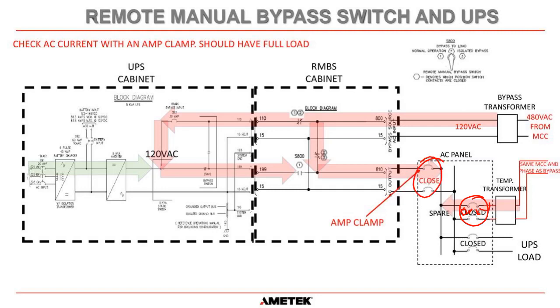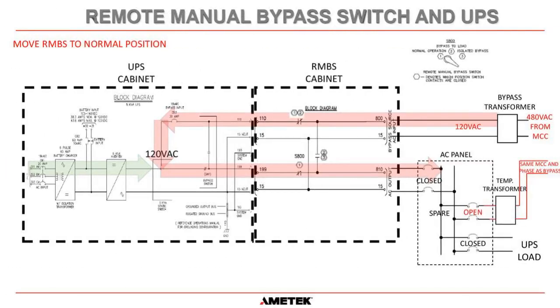We are now back in normal operation, and all we need to do now is get the UPS onto inverter to load. And to do that, we move the RMBS to the normal position first. Normal position here is position 1. Okay, normal operation. The only contact that closes is this one here, position 1. This one here was closed at position 2 and remains closed at position 1. So now power is flowing down this way here through the static switch, which is still in bypass.